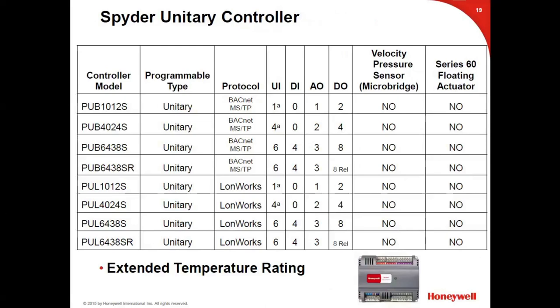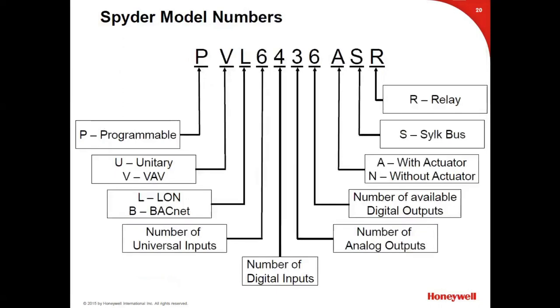The unitary controller follows the same naming convention. The BACnet and LON unitaries are shown together on one chart. In summary: 'P' = programmable, second character = unitary or VAV, third = LON or BACnet, then four digits for I/O point counts. If there's an 'R' at the end of the part number, it has relay outputs; without 'R', the digital outputs are triacs. All controllers now have the Sylk bus ('S'). An older version without Silk would be a very old controller.